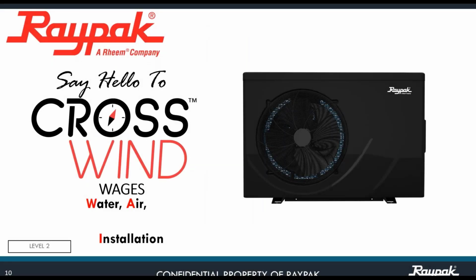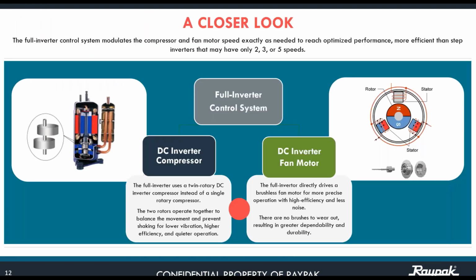Okay guys, so welcome to our classes. This is for water, air, gas, electrical, and service and installation. A closer look of a full inverter control system, because we are going to be seeing today just the inverter type. The compressor and the fan motor speed is exactly the speed that it needs to reach an optimized performance. So both of them are going to be going at the same speed. And this is more efficient than the step inverters that may only have 2, 3, or 5 speeds.